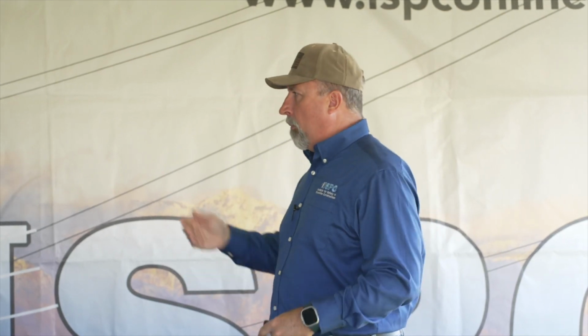In this last instance, they secured that extra ground with some ropes, loosely tying those things. You don't want to tie them tight, and you don't want to coil your grounds around steelwork. I've seen it happen—someone connects their ground, wraps it around the steel a couple times, then goes to the conductor. You just created an inductor, a coil, and that's going to be a problem. So we don't want to do that, but in this video they just used structure around the ground to keep it from moving quite as violently.